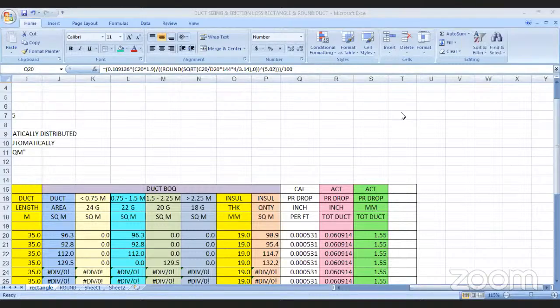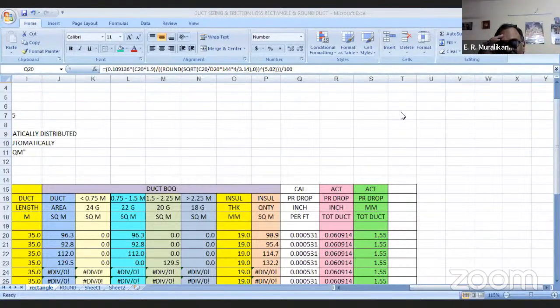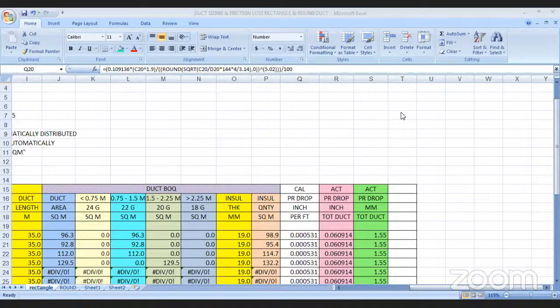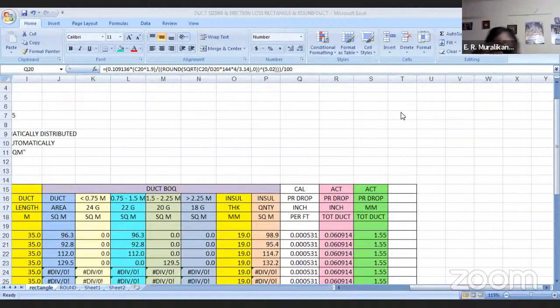First of all, I thank Mr. Murli for the nice session. You were talking about the sizing of the supply duct and the return duct. I understand the return duct will be a little higher in size than the supply duct, because the temperature of return air will be slightly higher, which will raise the volume of the return air, and that higher volume will pass through a lower area of the return, considering the velocity to be the same. Am I correct? Actually, theoretically, people say so, but actually it is not.